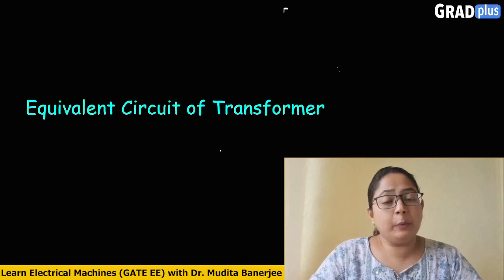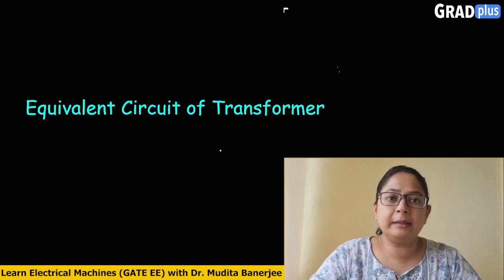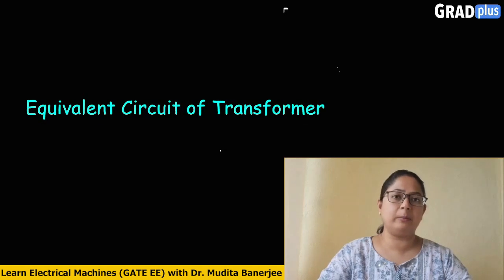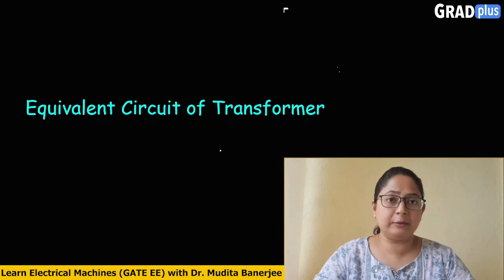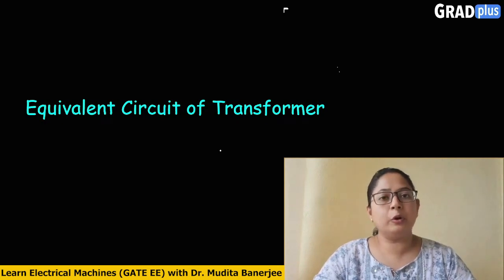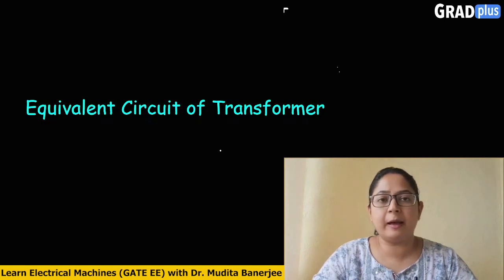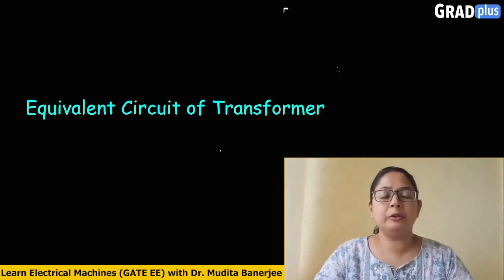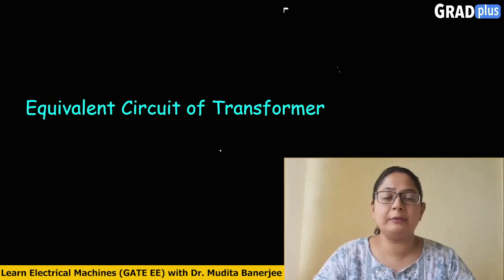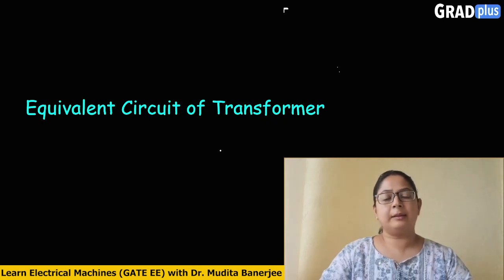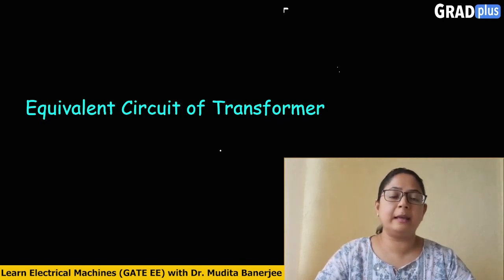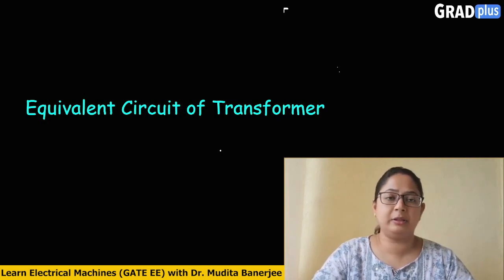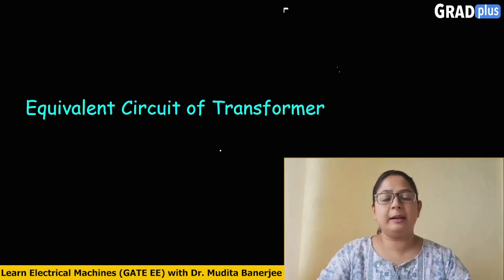The equivalent circuit of a transformer also tells us about the percentage impedance — the value of percentage Z of a transformer. When we install a transformer in an existing power system, the matching of percentage impedance value with other transformers already in operation and connected in parallel is also very important. That is why the equivalent circuit of a transformer is a very important topic if you are going to be a design or construction engineer in the electrical industry.